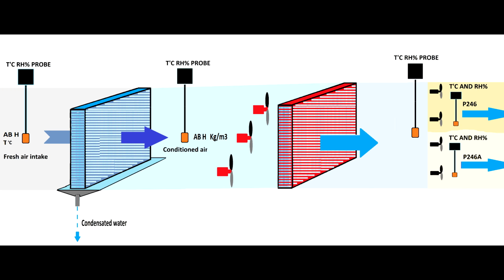And if you provide the same air change rates, then if the heat load is not well calculated, you will hit the jackpot. You will never be capable of having the proper temperature in these rooms. Some rooms will get hotter, some rooms will be cooler, some rooms will have a higher or lower relative humidity, and as I say, there's no middle way here. There's nothing you can do to control it unless you have either recoolers or reheaters.